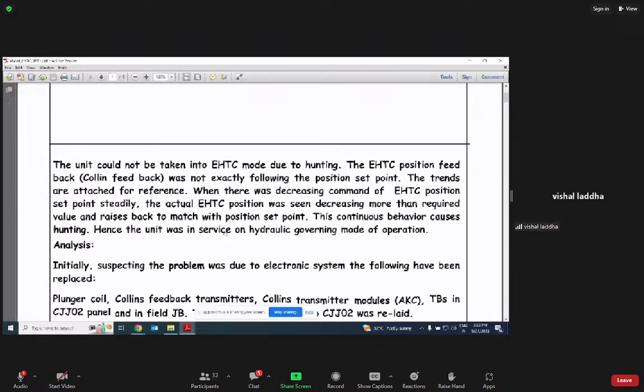Hunting means if our command is 50%, position set point is 50%, but the transmitter feedback is continuously hunting. Secondary oil is also hunting. So the EHTC position feedback was not exactly following the position set point. The trends are attached for reference. We will discuss the trends.